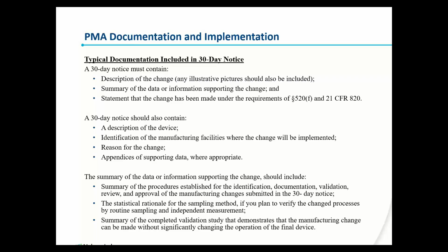And there is a great FDA guidance document, as I had on the previous slide. But once again, it goes back to, you're going to want a description of that change. You're going to want a summary of the data supporting the change. A statement, and this is a little outside what you would need for a 510K, but the change has been made under the requirements of 520F and 21 CFR 820, which is your quality system.